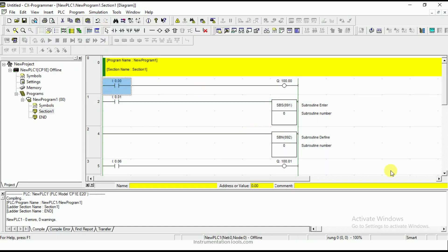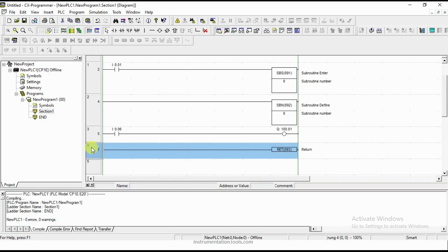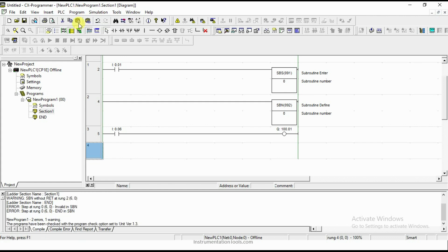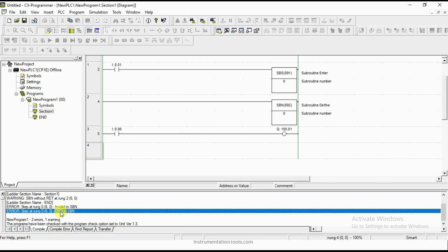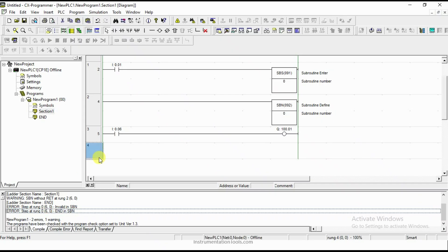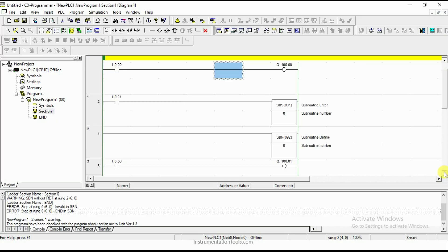The normal rung outside the subroutine works independently — you can turn it on or off whenever you want. This is how subroutine works in Omron PLC. What if you are not using the return condition? Let us compile and see — there is an error: 'Invalid in SBN; END in SBN.' So, return is mandatory; without it, you cannot perform.